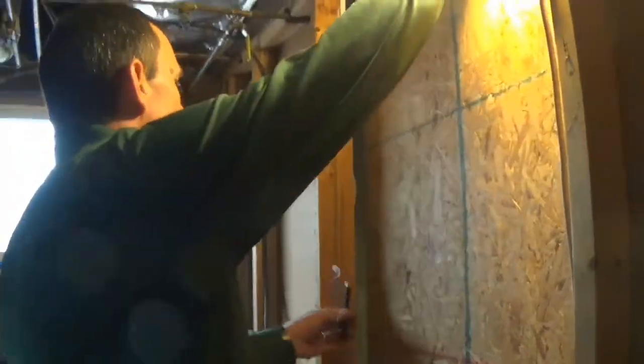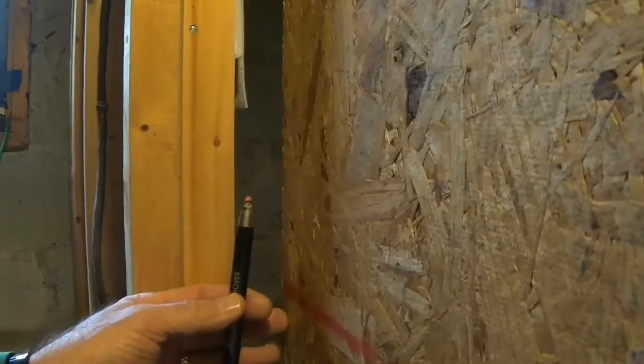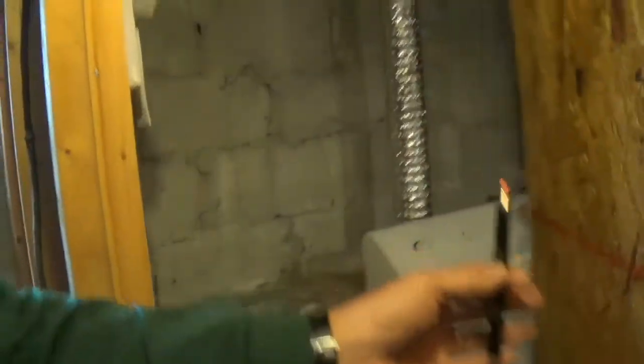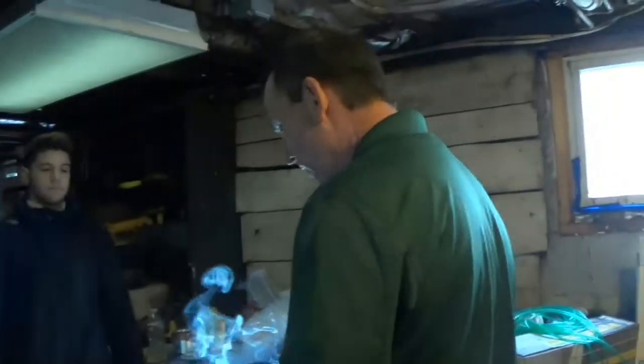Don't try this at home, don't walk backwards down the stairs, but so far the door from the basement has been left open, and this door from the combustion appliance zone is going to want to be left open because the smoke is blowing away from me, it's not blowing in my nose. So that's what we did to create the worst case depressurization for this combustion appliance zone that we're now standing in.